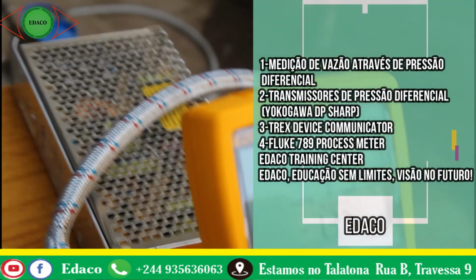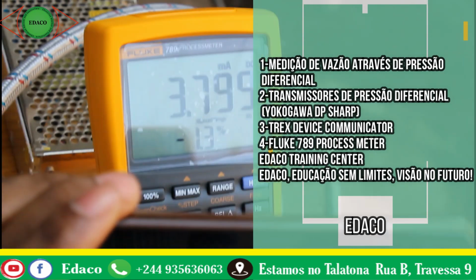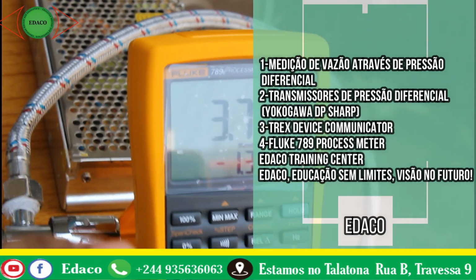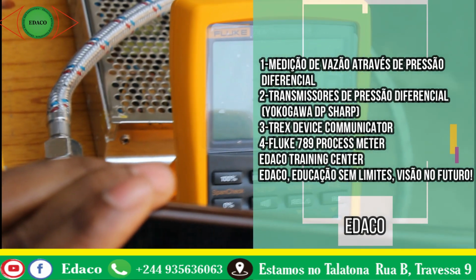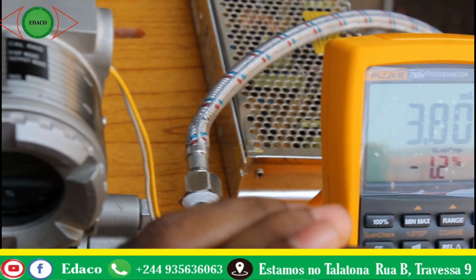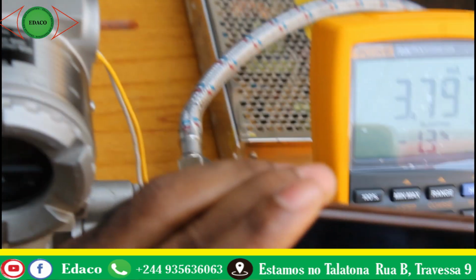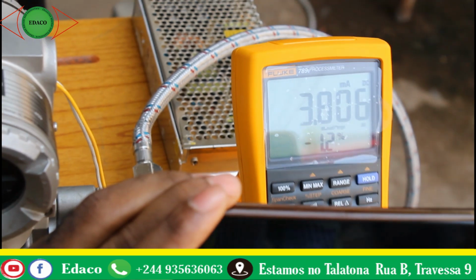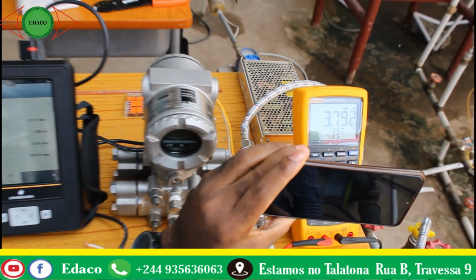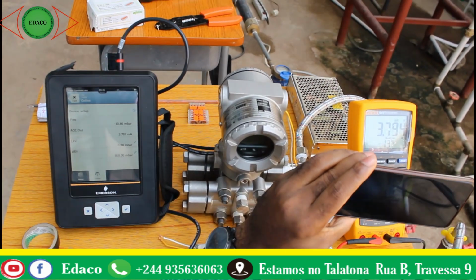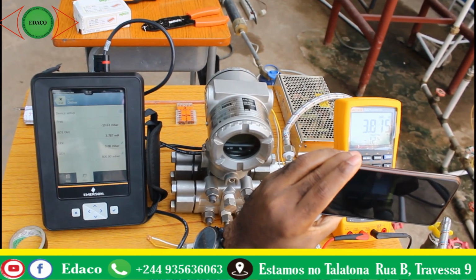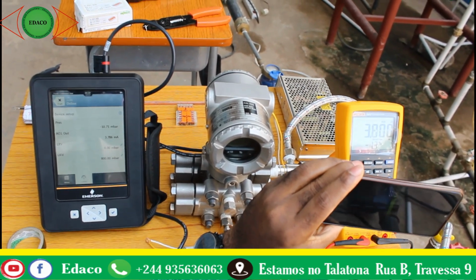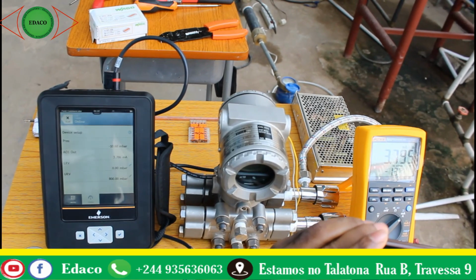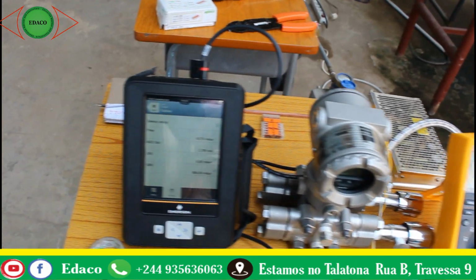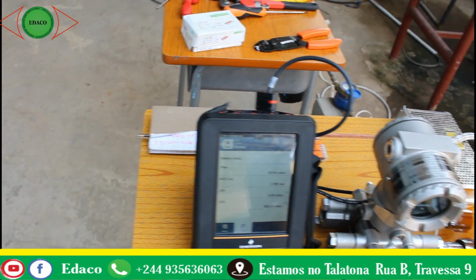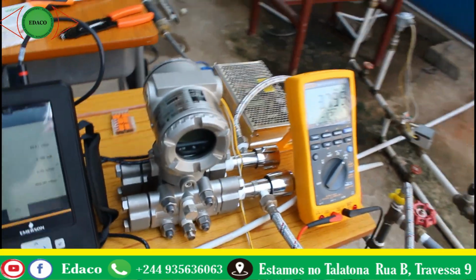We're going to bring this into our PLC system, and then to our HMI and SCADA system. There we will have the square root extraction in the process, so that it can compute the signal versus the flow rate in our system compared to the differential pressure. Right now there is no pressure because the pump is shut off.